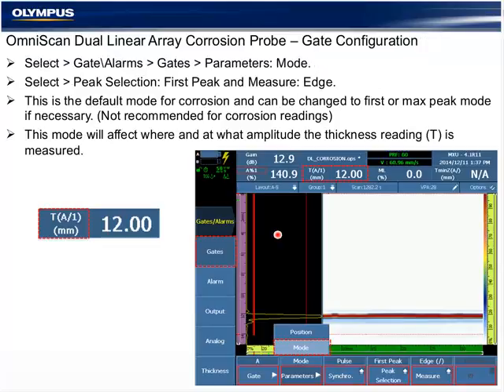The gate mode is already configured for optimized inspection in the default files. It uses a first peak selection measuring edge. So within gate A, the first peak in the gate and the leading edge of that gate, right where my laser pointer is at now, is where the reading is taken. Because we're not using auto gain correction, the amplitude of that signal in gate position will have a slight effect on the thickness accuracy. Using the normal defaults under very typical conditions, 0.25 millimeter accuracy should be well within the range of the inspection without much optimization of the UT or gate position for the range of thickness listed for each file.